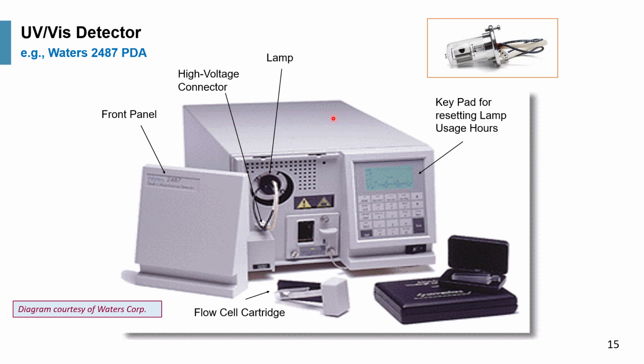if it's aging, or if you get very high noise, is to turn off the power switch. And you also need to pull out the plug from the end, make sure that it's not plugged in, just as a safety precaution. You open up the front panel, and obviously before you take out the old deuterium source, make sure you have a new source available. And there's an electrical plug, which is a quick disconnect to disconnect it from the power source.